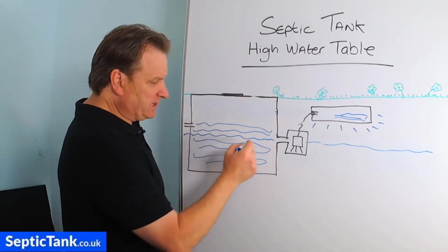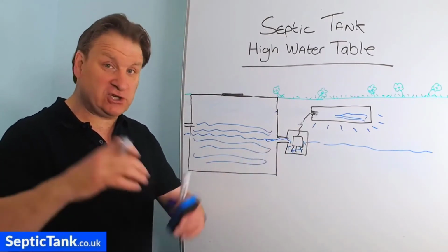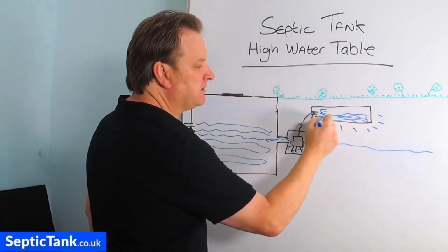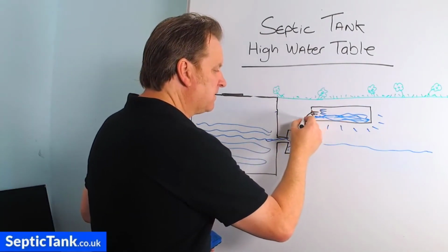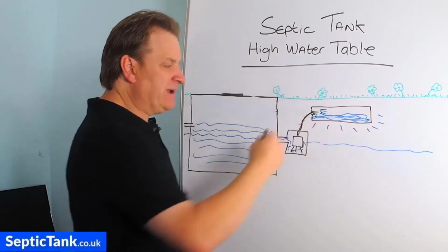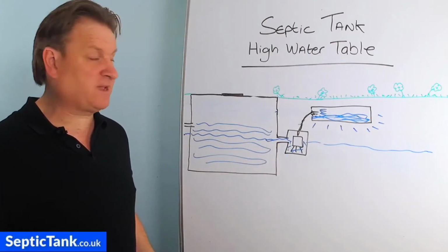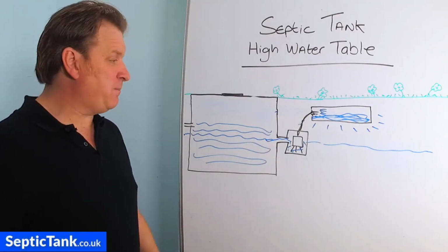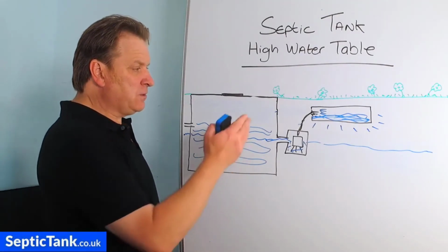So you get a bath load of water come here, a bath load of water will come into the pump chamber, and then they usually work on a float switch. It'll kick in, and then it will pump a bath load of water into your soakaway there. And then, as we saw before, there you go, that's your 1.25 inch pipe. As we saw before, that water will then just soak away naturally into the soil. So these pumps are normally on for about half an hour a month, something like that, because if you imagine, they can pump thousands of litres out every hour. So a bath load of water will just be pumped out literally in a minute or two. And so that is a very good option.